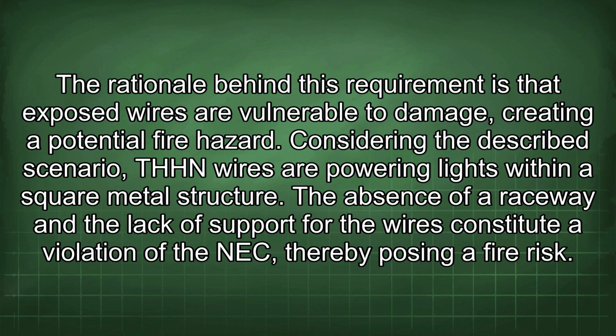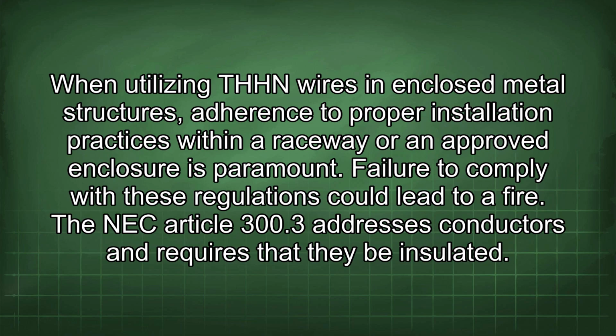Considering the described scenario, THHN wires are powering lights within a square metal structure. The absence of a raceway and the lack of support for the wires constitute a violation of the NEC, thereby posing a fire risk. When utilizing THHN wires in enclosed metal structures, adherence to proper installation practices within a raceway or an approved enclosure is paramount. Failure to comply with these regulations could lead to a fire.